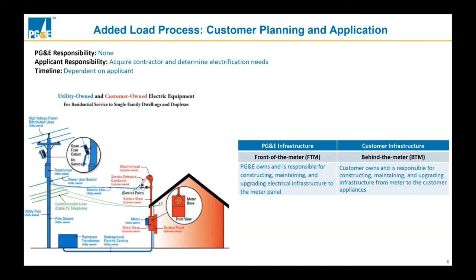This is where we get to the dividing line between customer side and utility side infrastructure. The meter is owned by PG&E, and everything behind the meter is considered owned and maintained by the customer. I should have said this at the outset, but it's important that the distinction between the infrastructure here isn't actually uniquely determined by PG&E. It's explicitly detailed in Electric Rules 15 and 16, which are governed by the California Public Utilities Commission.